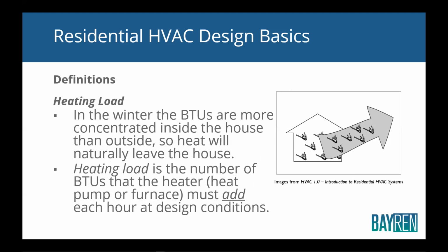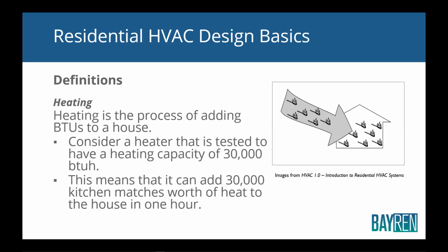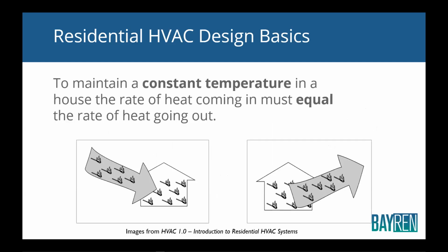The heating load is when the house is warmer on the inside and colder on the outside, so heat is naturally going to move from warmer to colder, so you're losing kitchen matches. So the ability to calculate how fast that's happening is a load calc. And then when you're heating a house, you're replacing those kitchen matches. So your furnace needs to replace those kitchen matches at least as fast as they're escaping if you want to maintain a comfortable temperature. So to maintain a comfortable temperature in a house, the rate of heat coming out of the house must equal the rate of heat going in. And the only way to know that is to calculate it and do a load calc on a house. If you oversize equipment, when that equipment comes on, it's putting the heat in much faster than it's coming out. So it's going to shut off quickly. So it's going to do what's called short cycling.